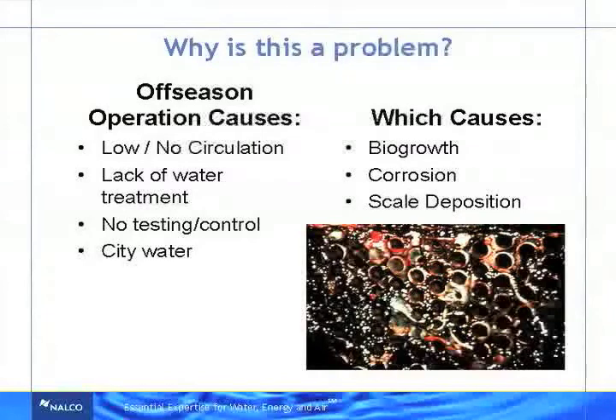The other thing you're going to see is no testing, no control. Go to a lot of buildings and ask to see their logs for the wintertime. Why do I need to test in the wintertime? The cooling tower is not even running. So a lot of people just don't even test or control during those months. The other thing that you're going to see in those periods is cleaning your cooling towers. When are you going to clean your cooling tower? In the off-season, when it's not running the most.